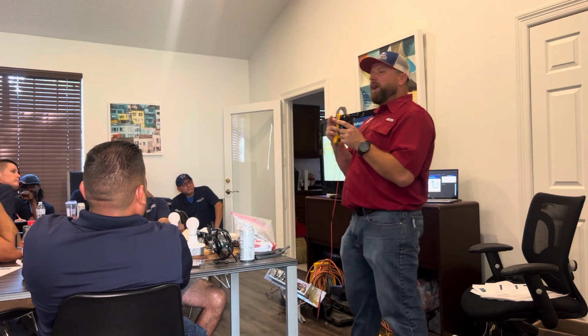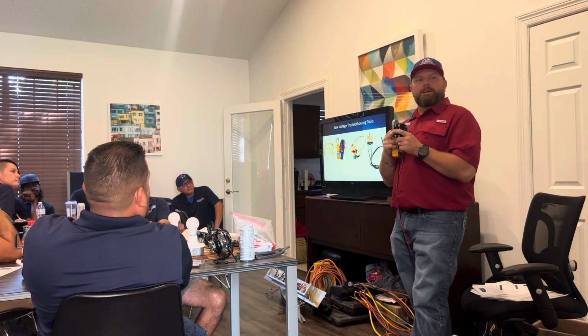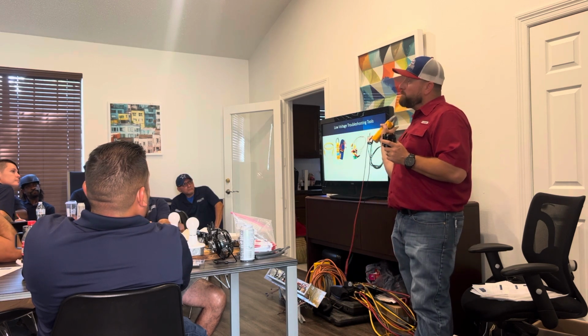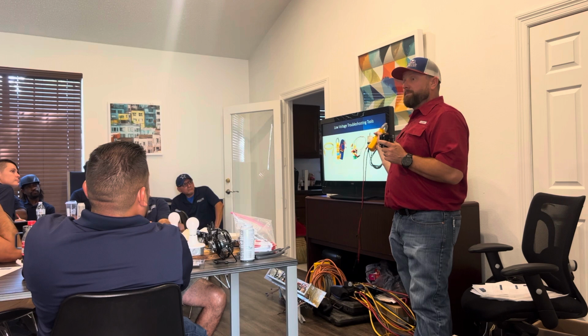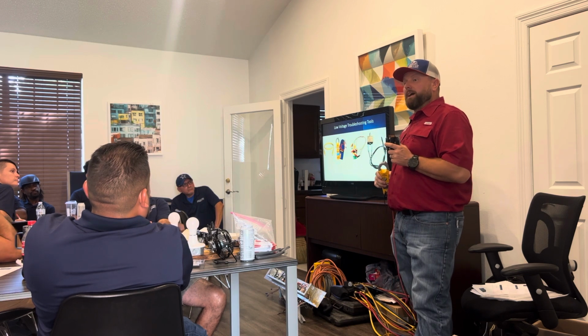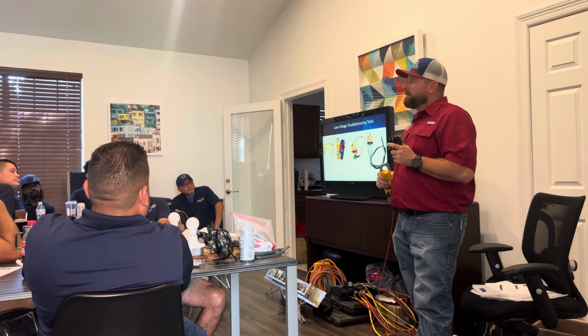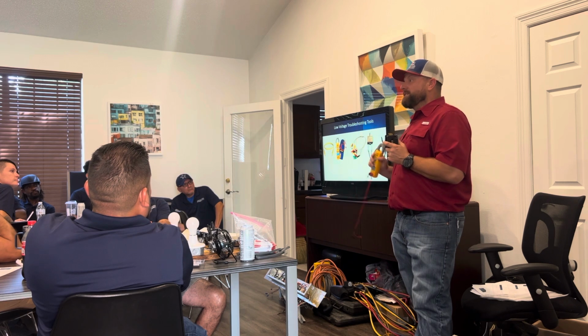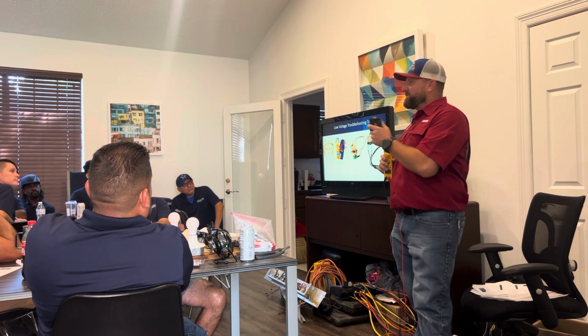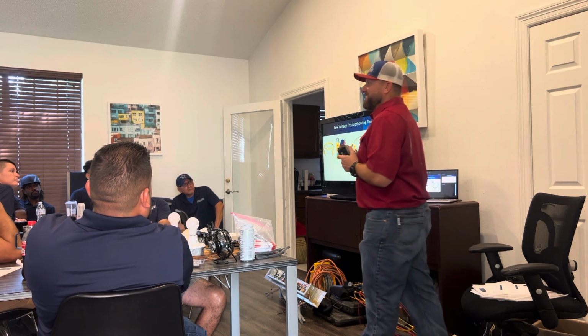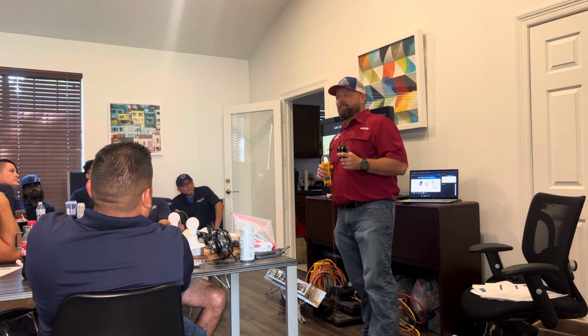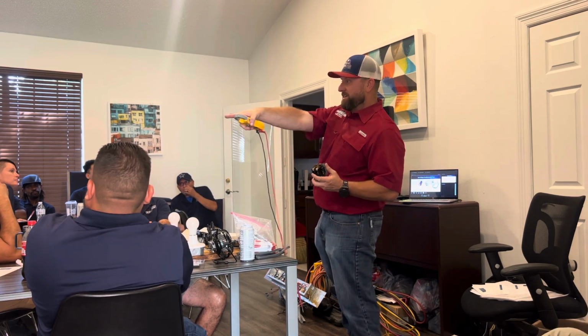So if you're not getting 24 volts to this, and you know you did it from the thermostat, where do you need to go check now? But you know you got 24 volts at the thermostat. We have 24 volts, there we go. Who said that? You get another one.